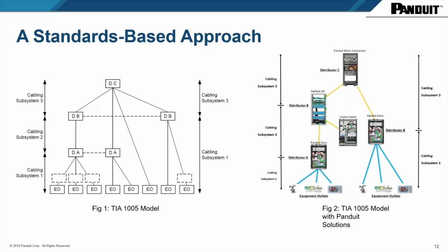As we go up, and you've seen it in the other slides, the color changes from red to yellow, and yellow means that it's a lower M.I.C.E category. So at the DC level, this is where you have what we call distribution C type enclosures, where we find data centers and everything else. This is the environment where you could use commercial grade product for all of it, including the enclosures.